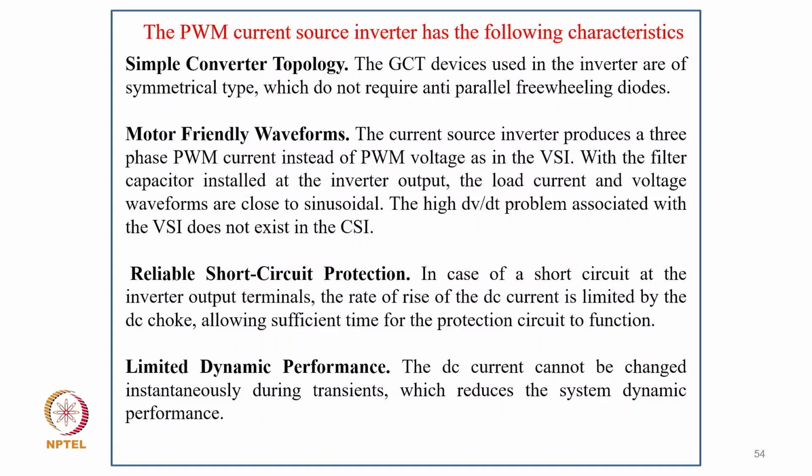And coming to reliable short circuit protection, in case of a short circuit at the inverter output terminal, the rate of rise of the DC current is limited by the DC choke, allowing sufficient time for the protection circuit to function.